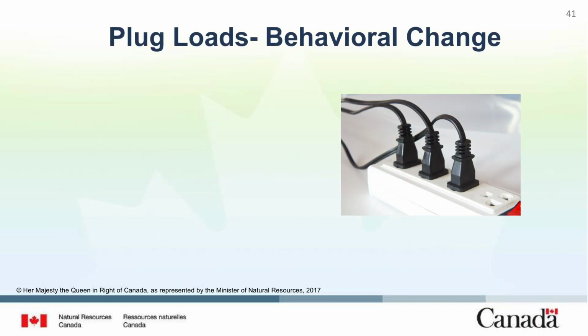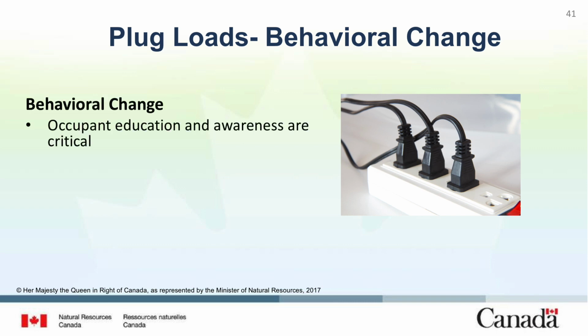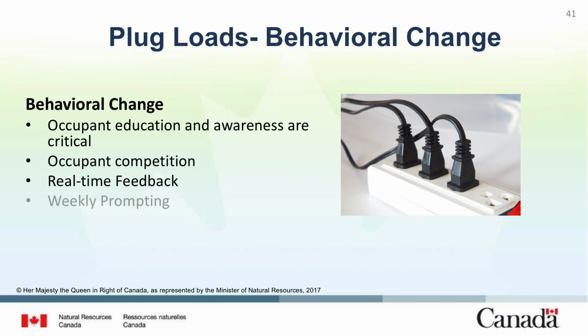Behavioral change is an important factor in reducing plug loads. There are a few ways to promote behavioral change. One way is to submeter plug loads so you can receive real-time feedback on how much plug load energy you're using. You can do weekly prompting or have an occupant competition. What you want to do is layer these strategies with controls. You want to make sure that you have plug load controls in place that are regulating usage and not just leaving it up to the tenant to regulate themselves.